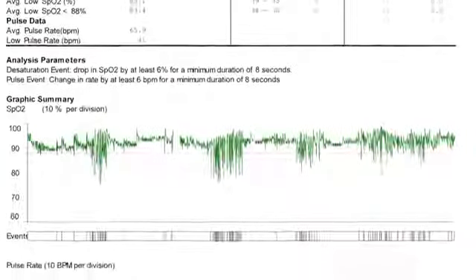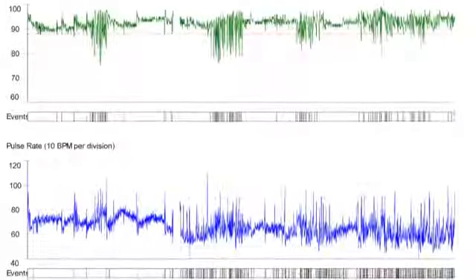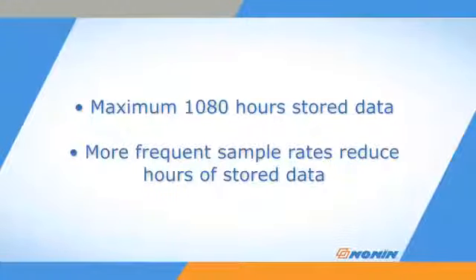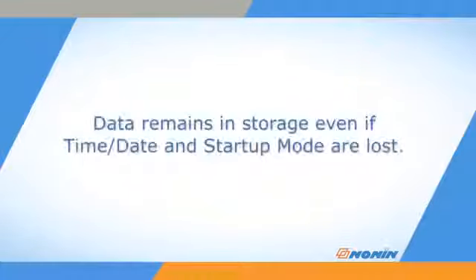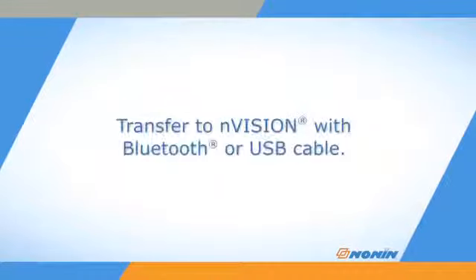The WristOx2 can store up to 1,080 hours of collected data, depending on the sampling rate. More frequent sampling rates reduce the number of hours for data storage, with 270 hours stored at every second data collection rate. Data remains on the oximeter even if the batteries are removed for more than 30 seconds and can be retrieved even if the time, date, and startup mode settings have been lost. The data can be transmitted or downloaded to nVision software via Bluetooth or a USB cable. See the instructions for use for more information on Bluetooth and nVision functions.